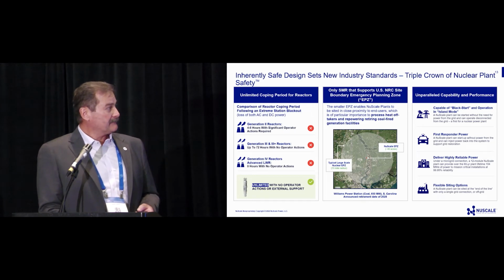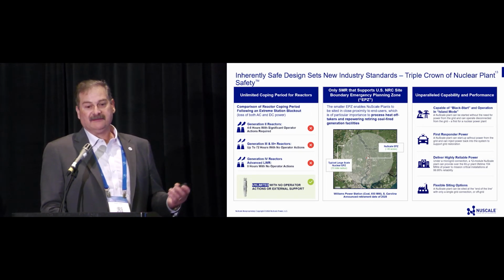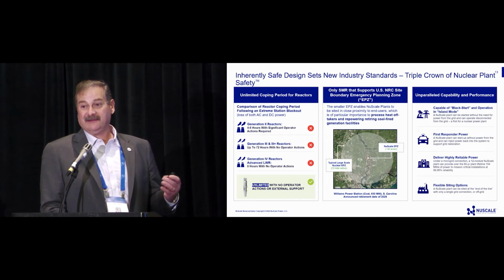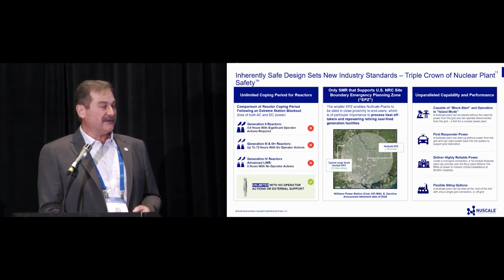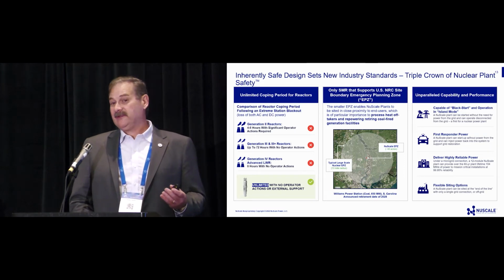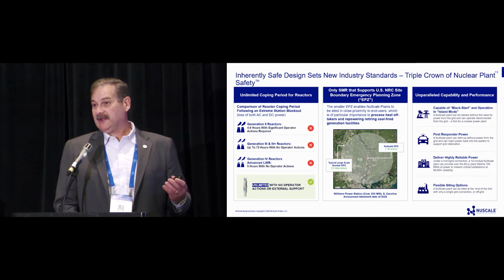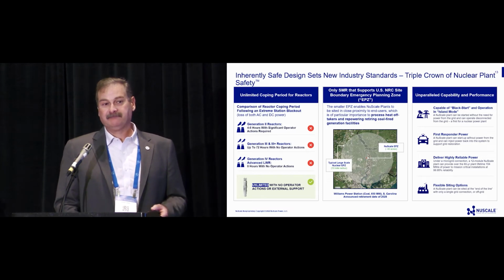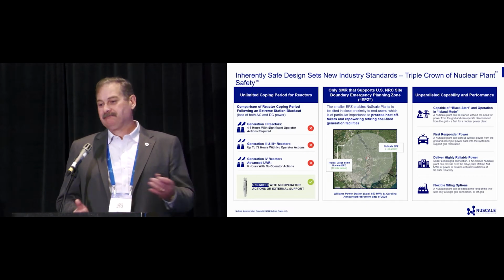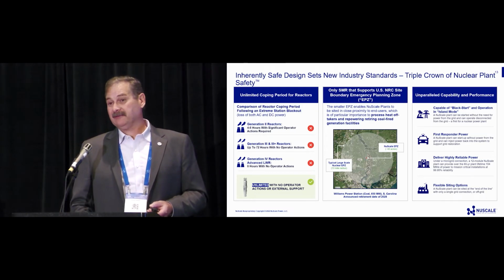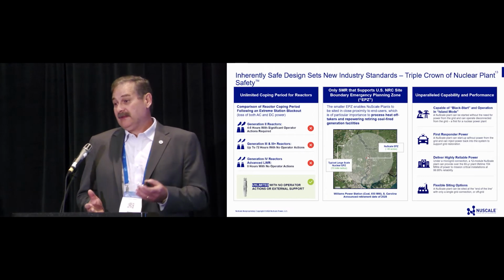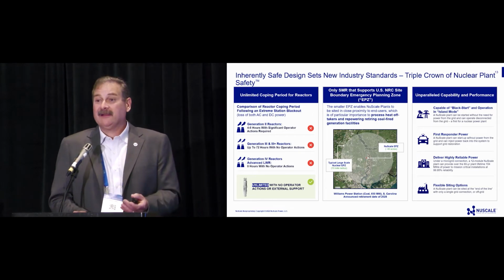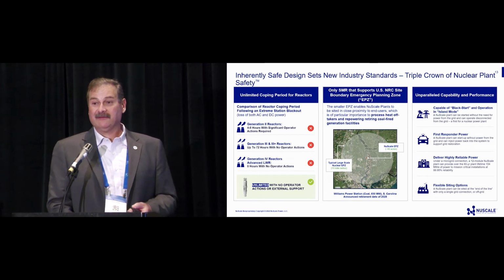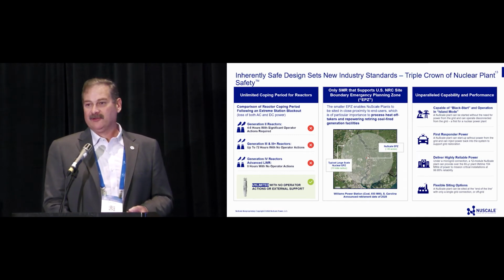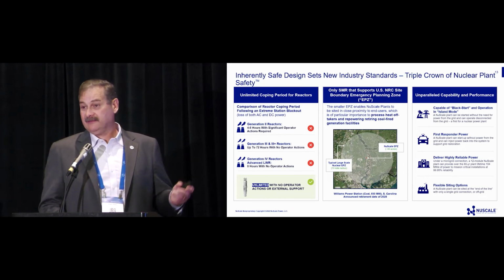So it saved us a lot of design and money when we went to design the electrical system because it was a lot easier to design. We still are going to have backup diesel generators, but they are not safety related. They're not required. They're just to give people confidence. Our batteries will monitor the plant for 72 hours after a loss of power. There's nothing that you can do to take an action, but you can monitor the status of the reactor for 72 hours. And then you could bring in diesel power and recharge those batteries so that you could get indefinite time.